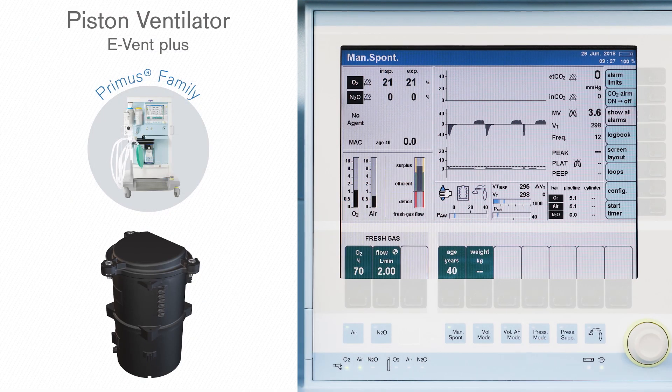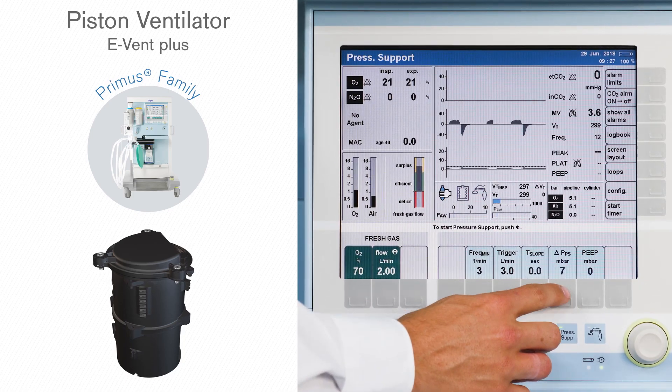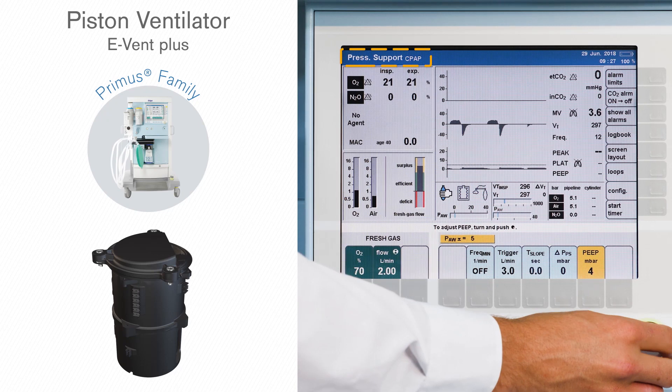The Draeger Primus family devices have a piston ventilator, the E-Vent Plus, which can also apply an active CPAP in pressure support mode by setting the pressure support to zero millibar and the PEEP to an adequate value.